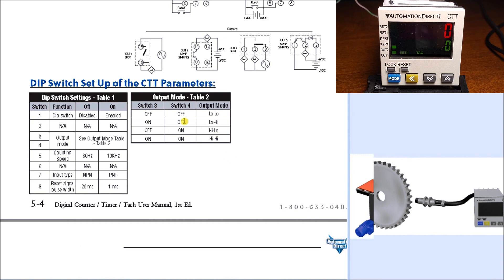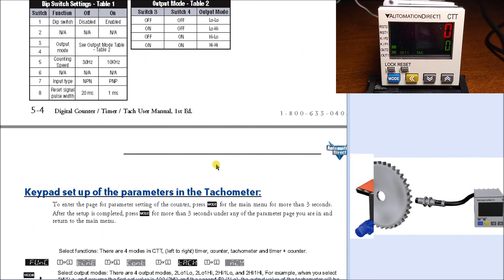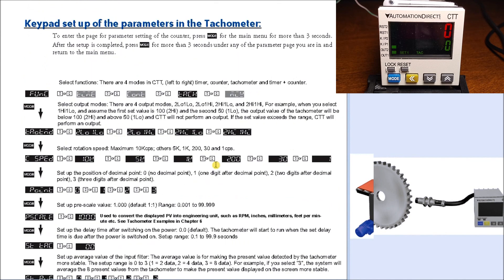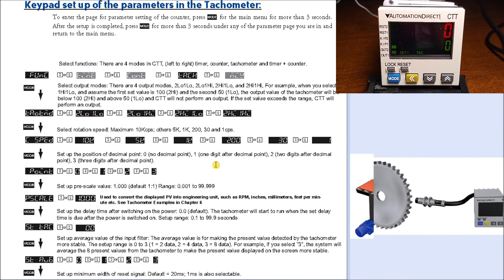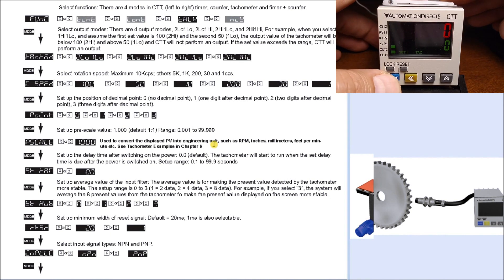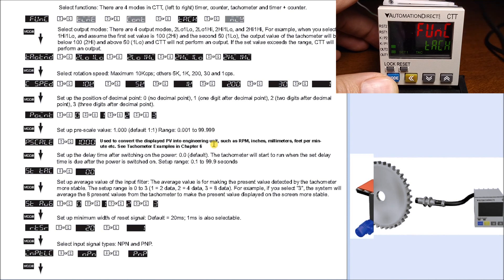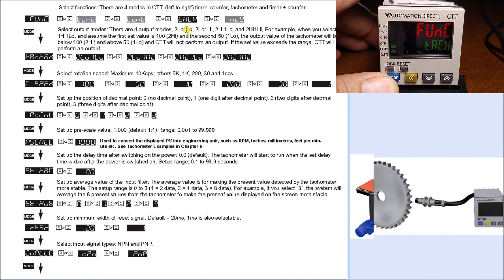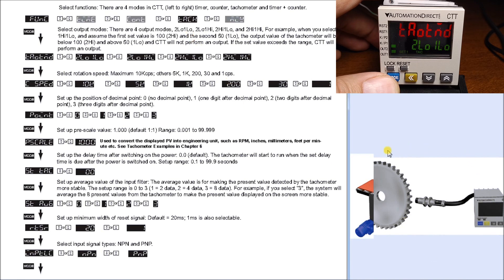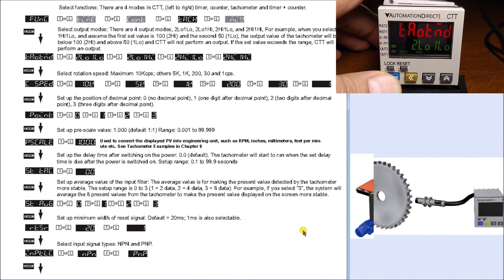Now we get into programming our CTT. We'll hold the mode key for three seconds to get into the programming function. The first one is our function, which is set for tachometer. Hit mode again and this sets our output mode - right now we have 2-low 1-low. Here's our timing chart for the 2-low 1-low as an example.